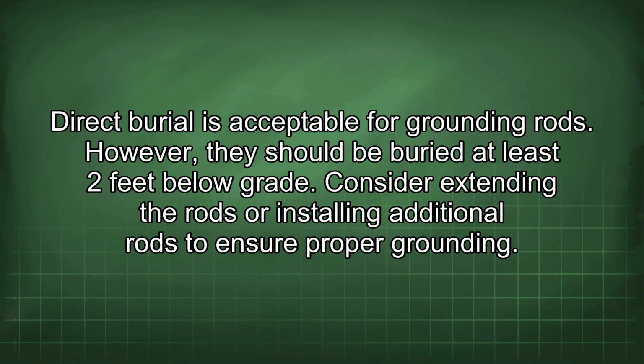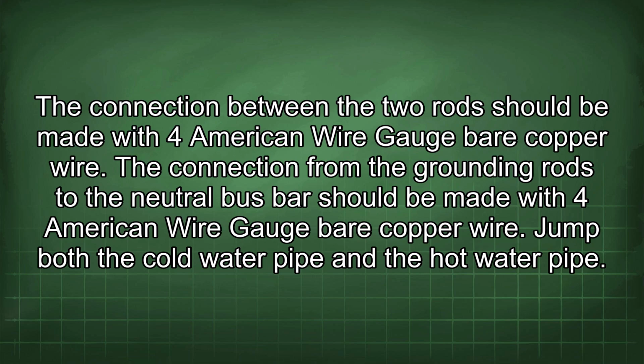Direct burial is acceptable for grounding rods. However, they should be buried at least 2 feet below grade. Consider extending the rods or installing additional rods to ensure proper grounding. The connection between the 2 rods should be made with 4 American wire gauge bare copper wire.